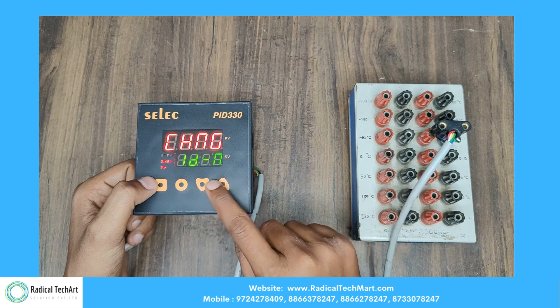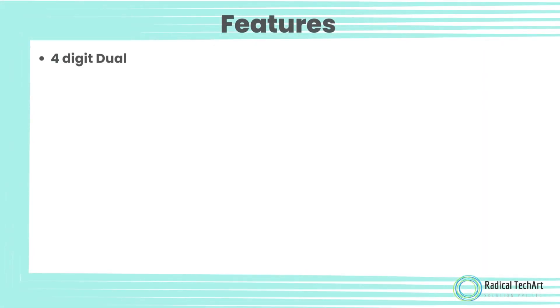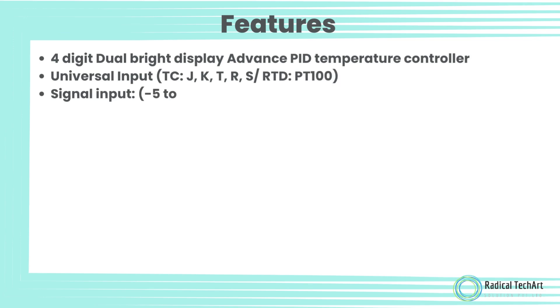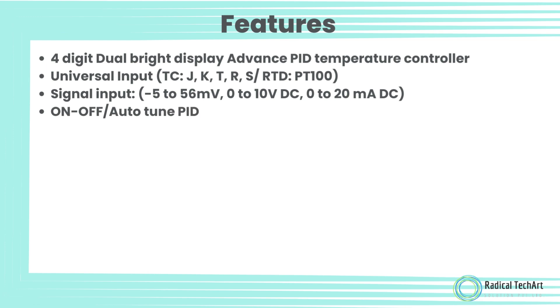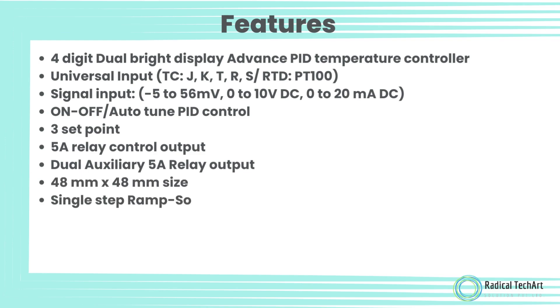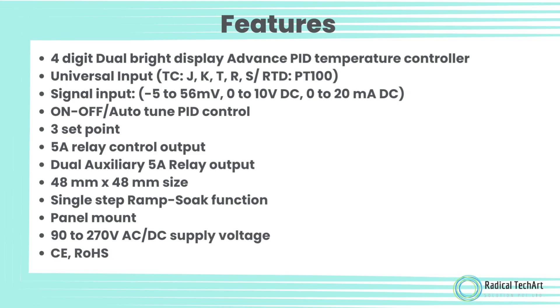Features include: 4-digit dual bright display, Advanced PID Temperature Controller, Universal Input supporting TC types J, K, T, R, S, RTD PT100, signal inputs from -5 to 56 mV, 0 to 10 V DC, 0 to 20 mA DC, ON/OFF and Auto-Tune PID control, 3 setpoints, 5-ampere relay control output, dual auxiliary 5-ampere relay output, 48mm x 48mm size, single-step ramp soak function, panel mount, 90 to 270 V AC/DC supply voltage, CE and RoHS certified.